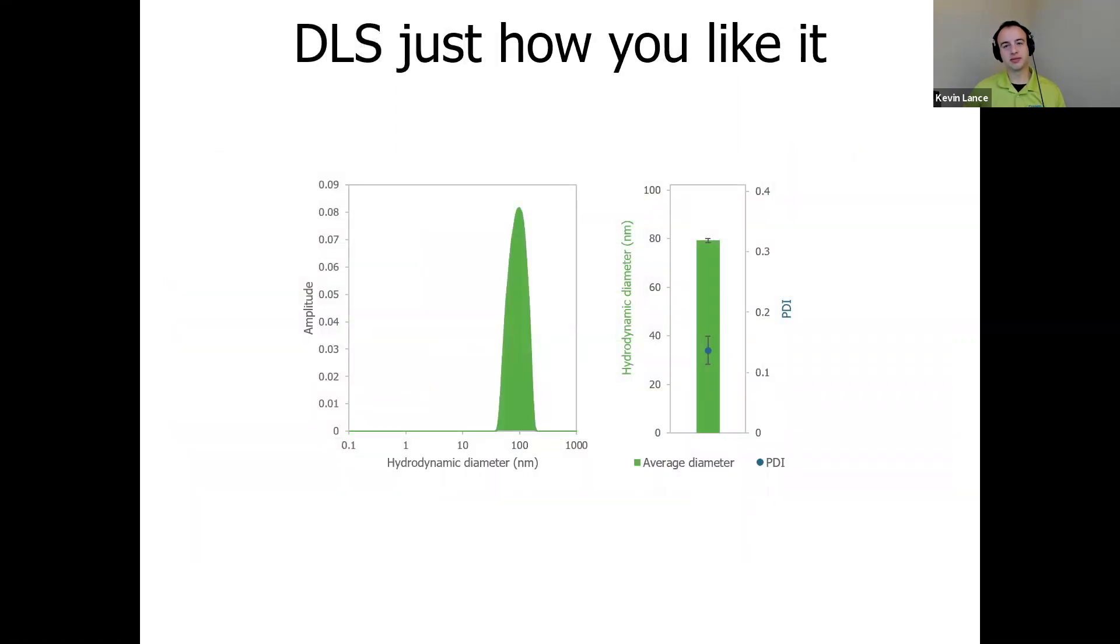Here we're looking at the results from a typical LNP sample. On the left you can see an intensity distribution. The mRNA LNPs tested here had an average hydrodynamic diameter of 79 nanometers plus or minus one percent, which is visualized by the green bar plot on your right and its error bar. Inside that bar plot you can see PDI value as a blue dot with error bars showing a PDI of 0.14 plus or minus 0.02. That's the nice kind of statistics you can get once you can run lots of replicates on DLS using Stunner.